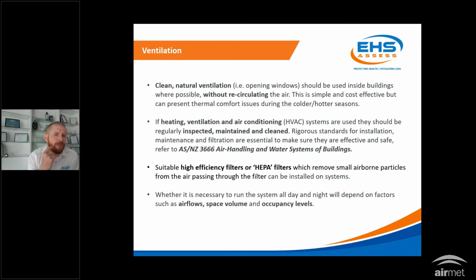If we do have the benefit of a heating, ventilation, air conditioning system, a HVAC system, it needs to be inspected, maintained, and cleaned. A lot of these systems are installed with little to no maintenance performed on them, and while they're supplying air to an environment, the quality of that air may be jeopardized. There is an Australian standard for air handling and water systems of buildings, referred to as AS3666, which has monthly, quarterly, and annual requirements for maintenance of your system. So ensure whoever manages your HVAC systems is maintaining and managing them as per the Australian standard.